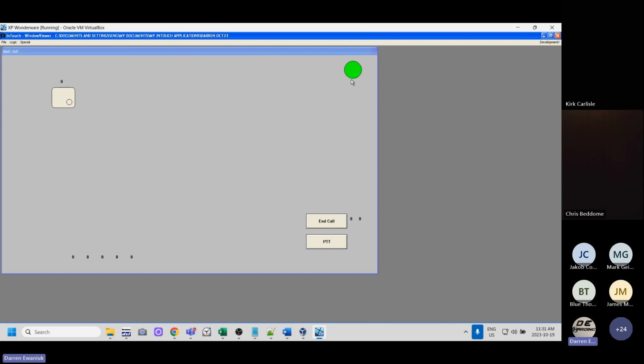I'm not sure how long this takes, but I will go and disconnect the Ethernet from it. And a few seconds later, you should see an update indicating that I've lost connection to the DCC. There we go. So now I've lost connection to the DCC. The connection status turns red. So as a programmer, that is the first thing I want to look for, is make sure I've got communication to and from the system.